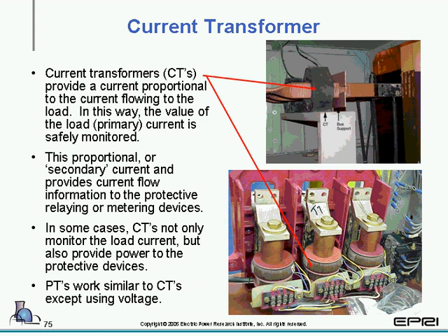And if we take a look at the upper picture, we'll see this is a medium voltage CT, and it's installed in the switchgear here. If we take a look at the lower picture, you'll see that we have CTs. Now these CTs are actually installed on the breaker itself. And if you look closely, you'll see we have 2 CTs. One CT is used to monitor the primary current, and another CT is used strictly to power the protective device.